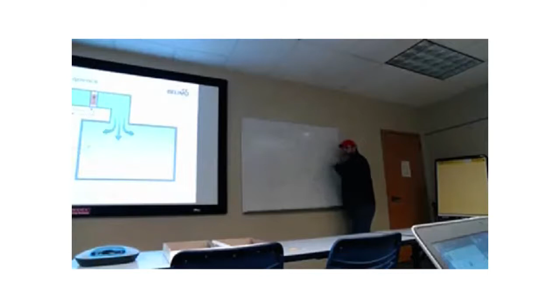Now we have one more signal, which we'll talk about today, where from the actuator to the controller, or to the head end, whatever it is, this is called position feedback. Well, in most cases, it's called position feedback. We actually have valves that will feed back on flow. We can actually get a flow output. But in general, the command signal is, I told you to do this, right? I told you to go here, like say for position. The actuator says, well, here's where I really am.